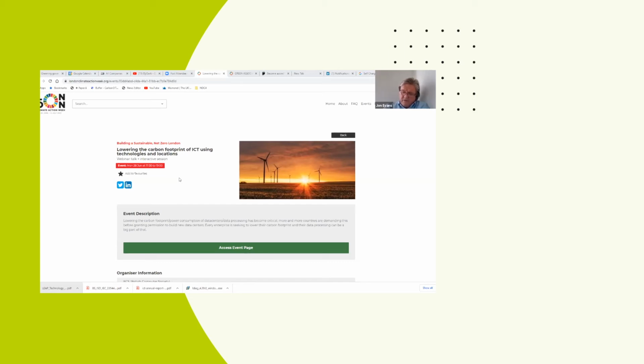The other thing you can do is actually shut down non-critical servers. If you had a battery for an hour instead of a diesel generator, you could automatically shut down non-critical servers over that hour and increase the autonomy time of the batteries. As the servers go down, the battery time increases. We did one at Leeds University many years ago, and we went from 200 kilowatts down to about 40 kilowatts over an hour's period. So the autonomy of the battery was 4 or 5 hours, which was more than enough for any outage.